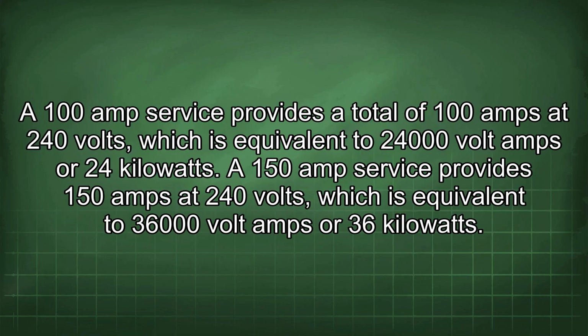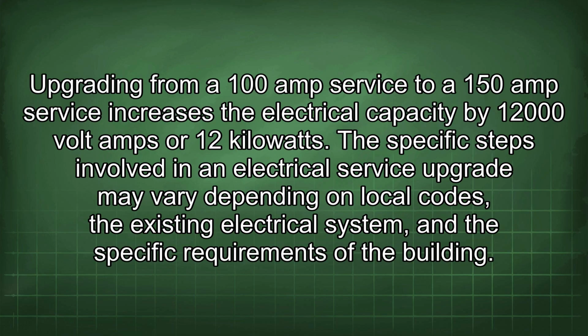A 100 amp service provides a total of 100 amps at 240 volts, which is equivalent to 24,000 volt amps or 24 kilowatts. A 150 amp service provides 150 amps at 240 volts, which is equivalent to 36,000 volt amps or 36 kilowatts. Upgrading from a 100 amp service to a 150 amp service increases the electrical capacity by 12,000 volt amps or 12 kilowatts.